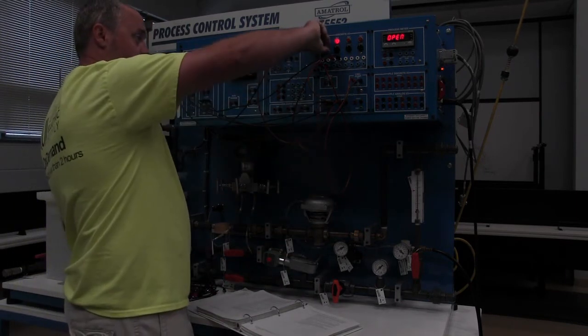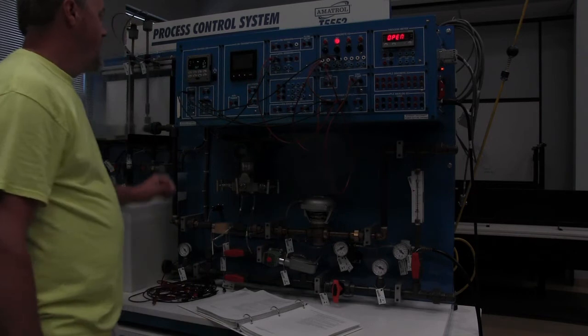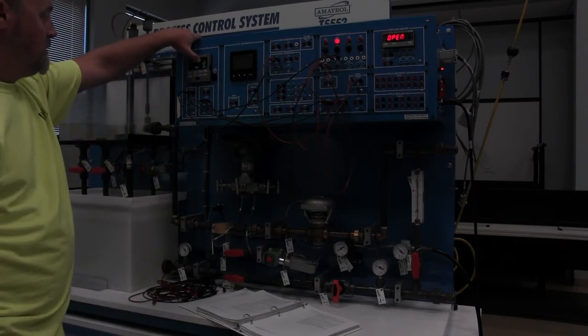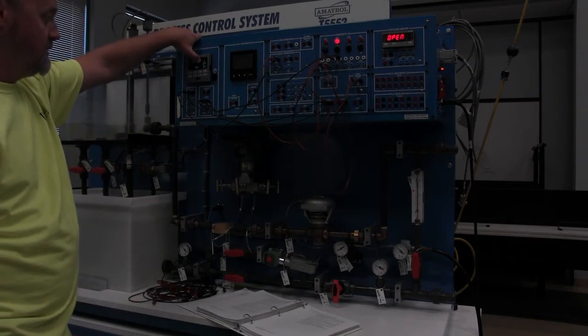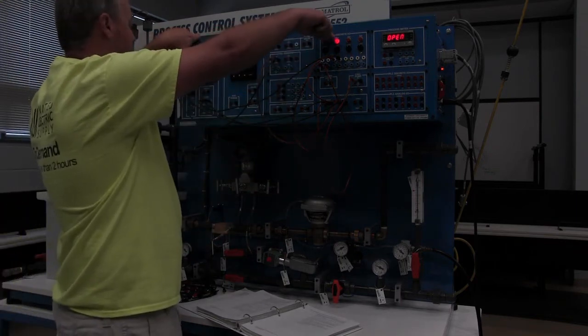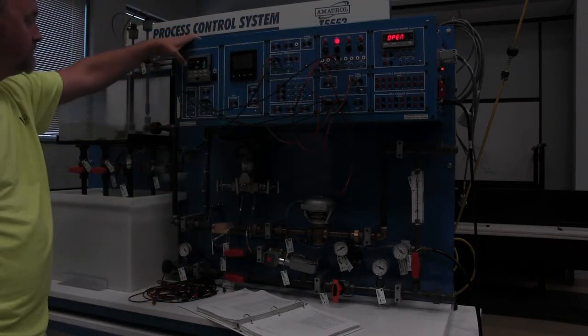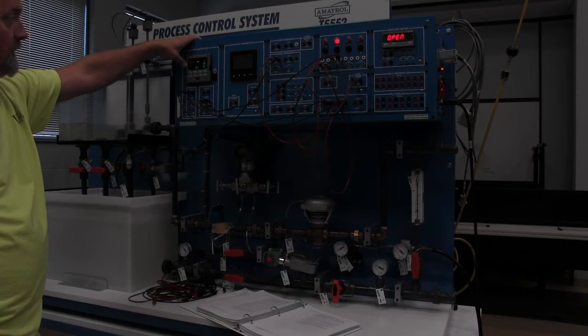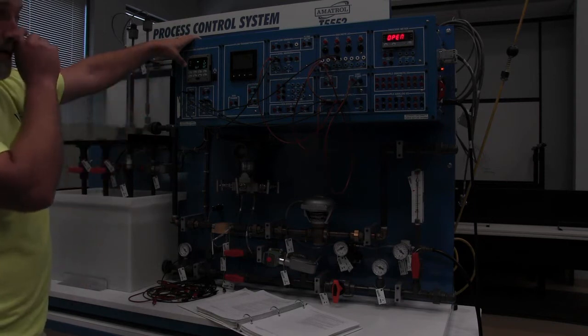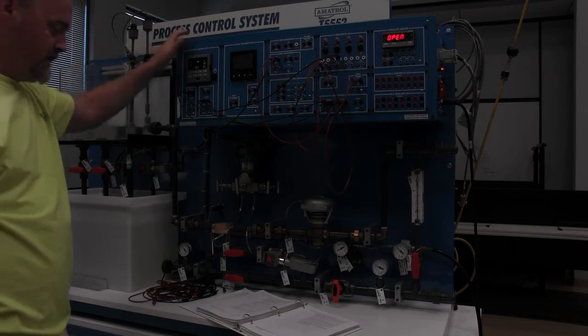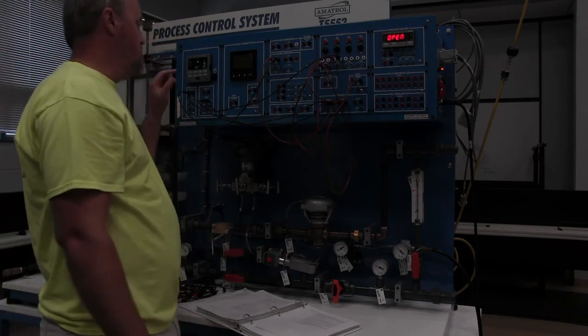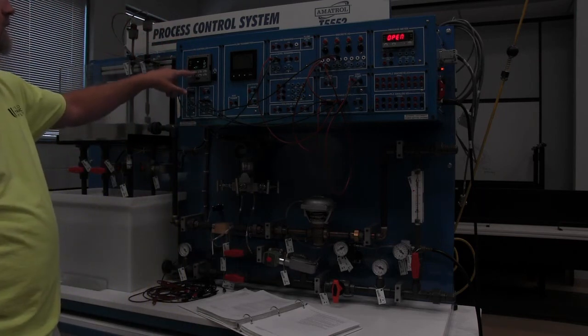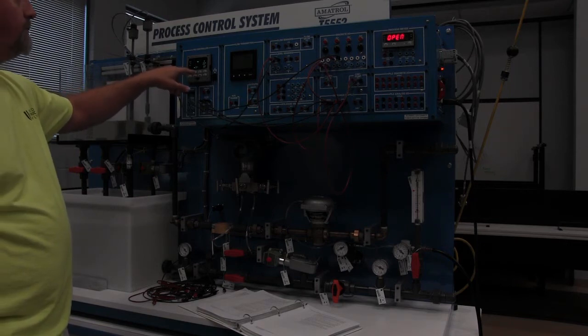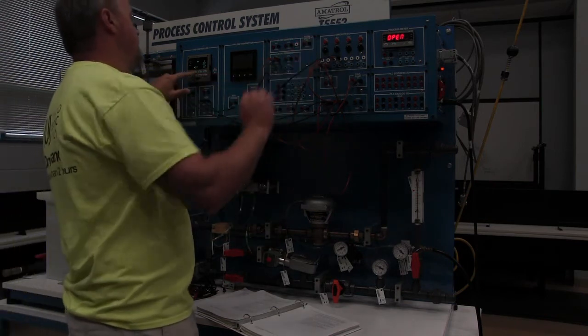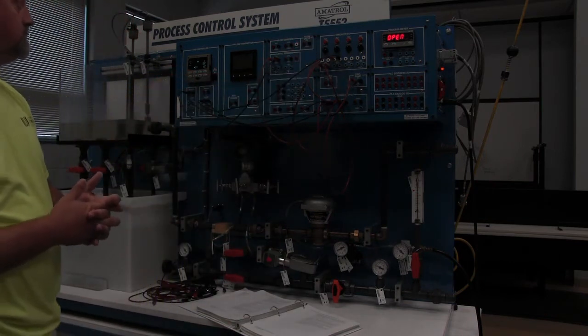As I turn selector switch 1 on, once we get above a 1.0, we're going to notice that our alarm light is going to go out. We were currently at a 1 and now at a 1.1. The alarm light has gone out. Once we reach a 5 set point, which was what our high alarm was, we are going to see that light come back on, indicating a high alarm.